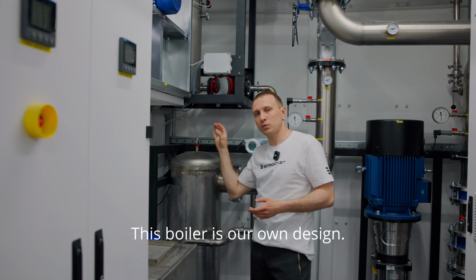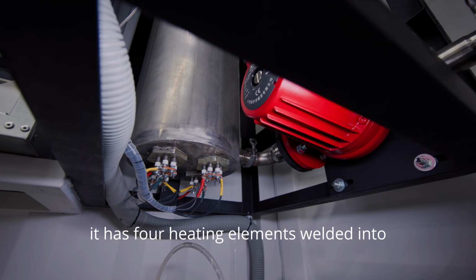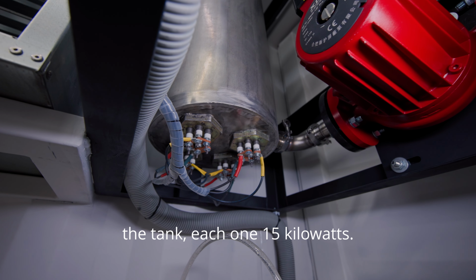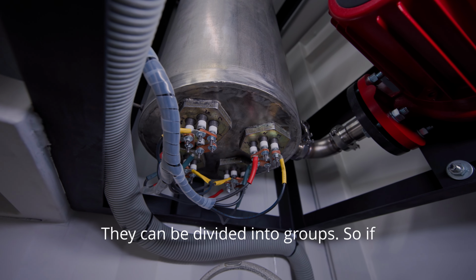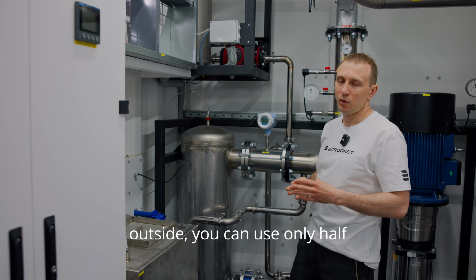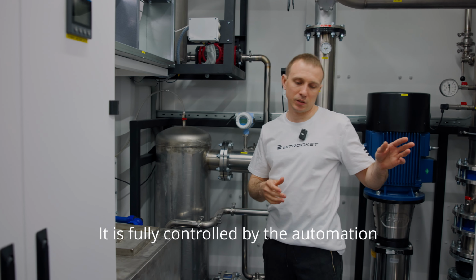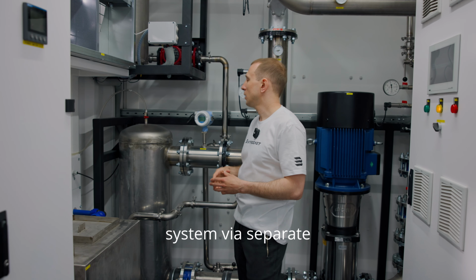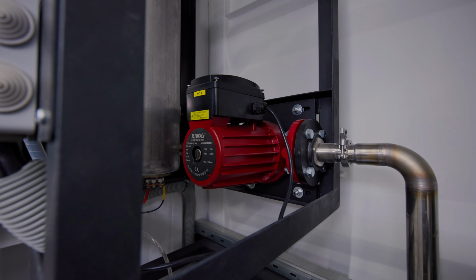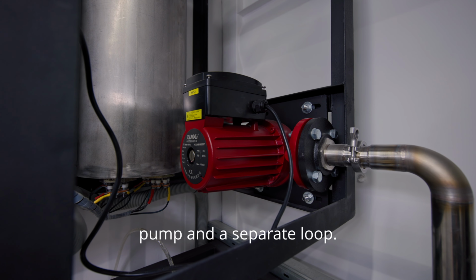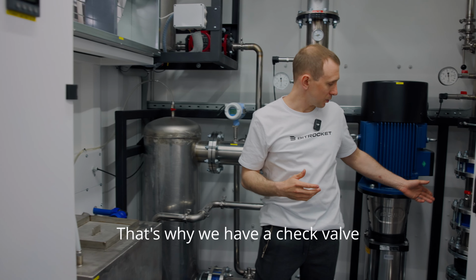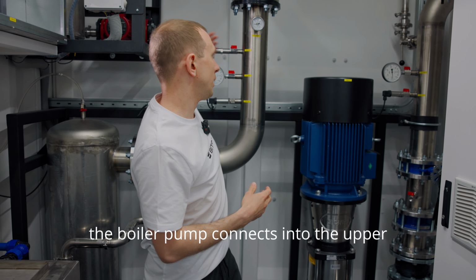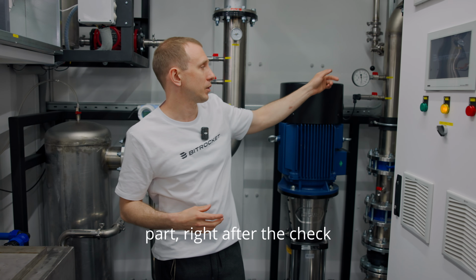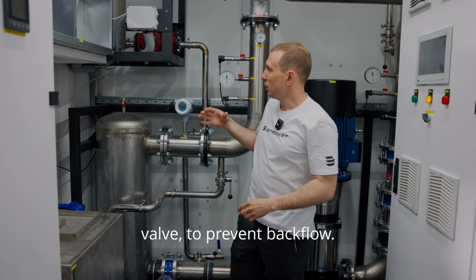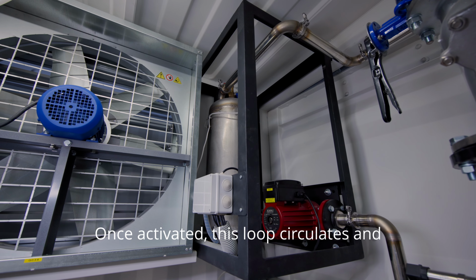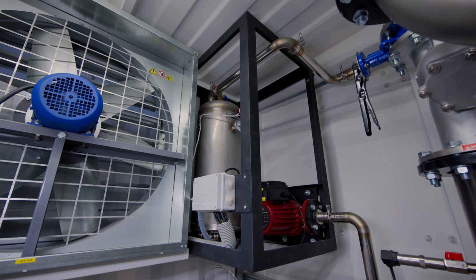This boiler is our own design. It has 4 heating elements welded into the tank, each one 15 kilowatts. They can be divided into groups. So if it's not very cold outside, you can use only half of them. It is fully controlled by the automation system via separate circuit breakers and contactors. It has a dedicated pump and a separate loop. That's why we have a check valve installed on the pump group. The boiler pump connects into the upper part right after the check valve to prevent backflow. Once activated, this loop circulates and heats the entire circuit evenly.